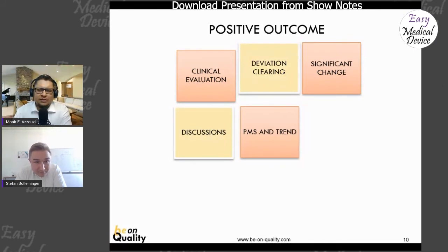I think this is a good discussion because a trend for one company is different than a trend for another company. So defining the trend is really important in your quality management system. For example, in one of my companies, if you had the same issue three times within the same period, that's a trend. Or if you have a 10% increase in issues compared to the last period, that's a trend. So you define what a trend is, and the auditor checks this against what you've already defined. You cannot just say a trend is a trend, because as I've said, it's different for everybody.